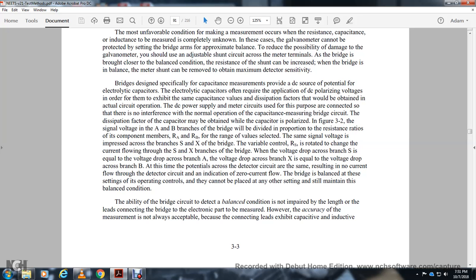Bridges designed specifically for capacitance measurement provide DC bias for electrolytic capacitors. Electrolytic capacitors often require the application of a DC polarizing voltage in order to exhibit the same capacitance and dissipation factor that would be obtained in actual circuit operation. A DC power supply meter circuit is connected so as not to interfere with the normal operation of the measuring bridge circuit.